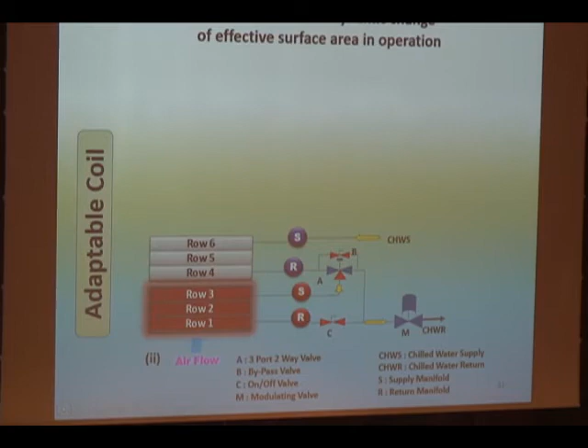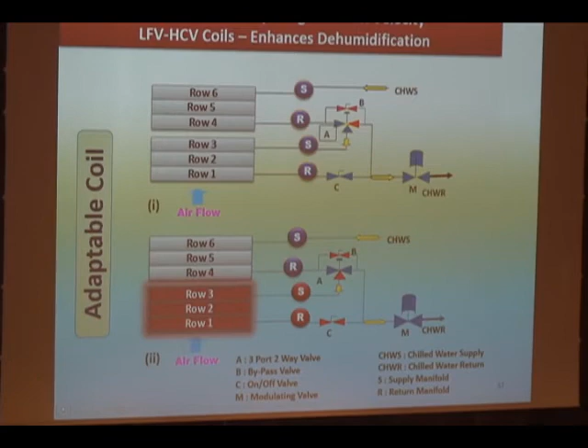It doesn't have to be a 4 to 3, it can be 6 to a 3. It can be a 6 to 4 or 6 to 5 or whatever we think is the right changing characteristics of the coil surface area. Now we combine this with another well-known, well-established theory that we are all aware of. If the airflow through the coil is at a lower velocity, lower Reynolds number, it helps improved heat transfer and mass transfer. If the chill water flow through the tubes of the coil is kept as high as practically possible, this is because too high a velocity, pressure drop increases, not a practical solution. So we call it this combination of low face velocity of the air combined with the high coolant velocity through the coil. Helps in getting the maximum dehumidifying performance of any coil.